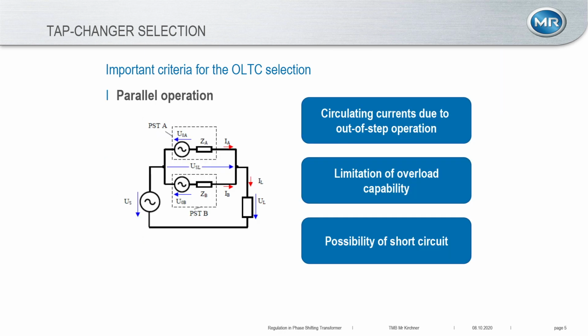What we see quite often is that phase-shifting transformers are operated in parallel. So if you operate phase-shifting transformers in parallel, you have to be aware of the fact that the on-load tap changers of both units are not always operated in a synchronous way. That's just not possible. There always will be a time delay. So if you have different voltages on your booster windings, then you will create a circulating current between the phase-shifting transformers. And this circulating current will add up to the load current on your phase shifter. For thermal reasons, that might not be the big issue for a certain time, but the on-load tap changer must be able to handle this current. So in many cases, we would ask our customer, is there any parallel operation planned? And if so, what are the circulating currents? Because we have to consider them.